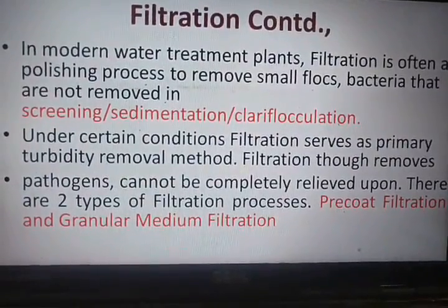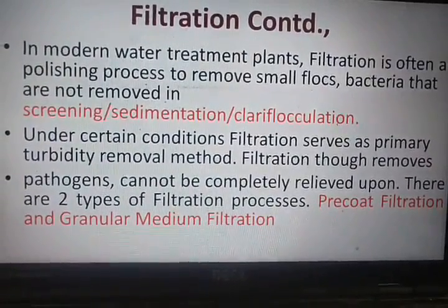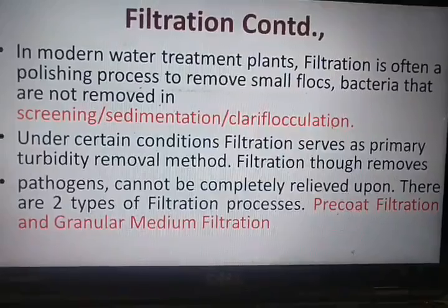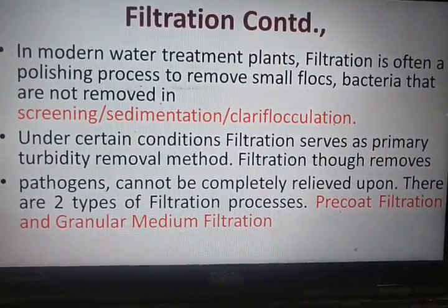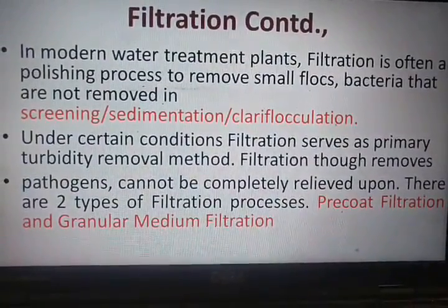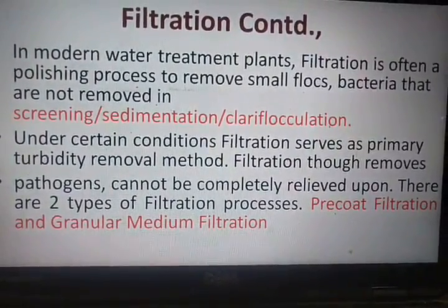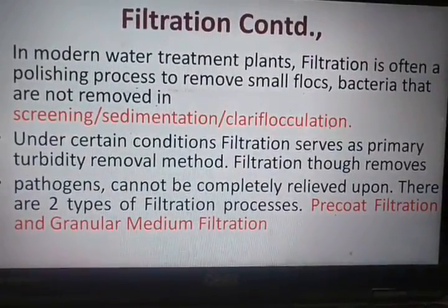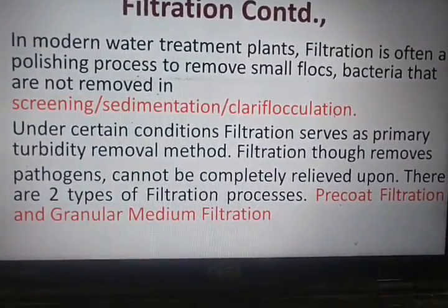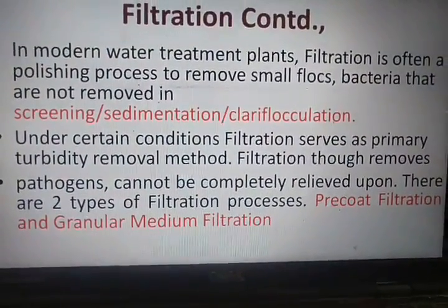Also, under certain conditions filtration serves as the primary turbidity removal method, because turbidity is usually caused by colloidal solids and suspended solids, and filtration removes most of the turbidity. Pathogens cannot be completely relied upon to be removed. That means it doesn't remove all the bacteria, so filtration must be followed by disinfection. There are two types of filtration process, called pre-coat filtration and granular medium filtration.